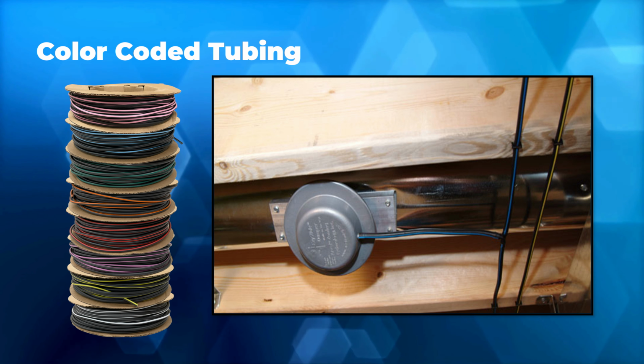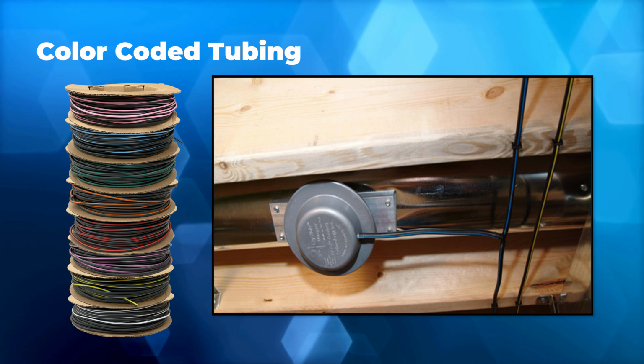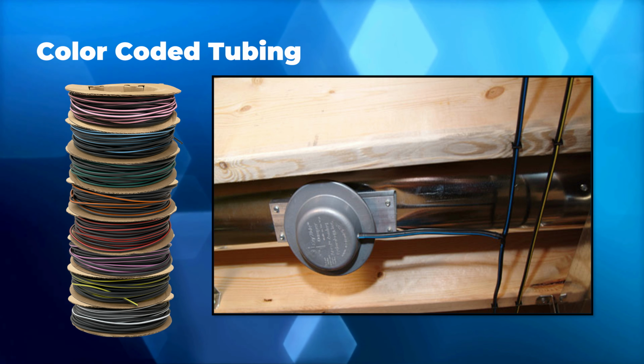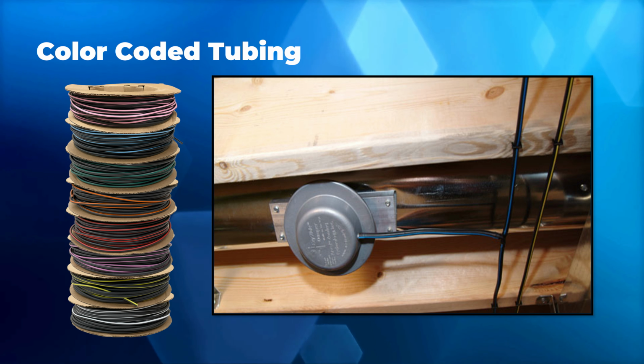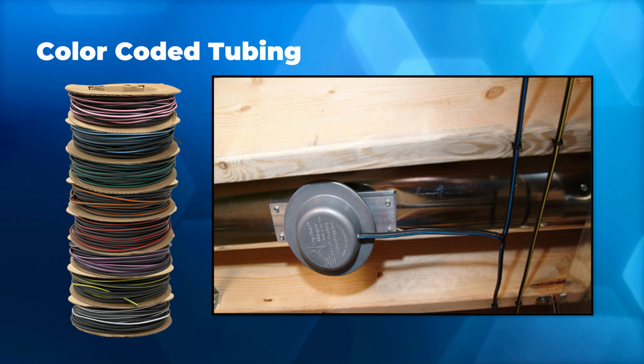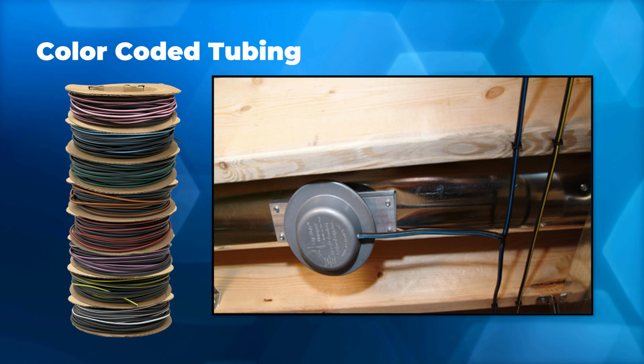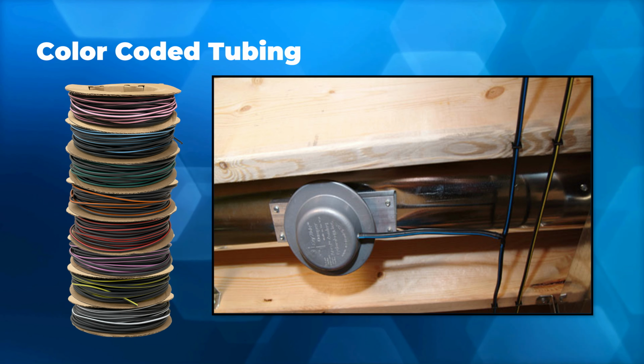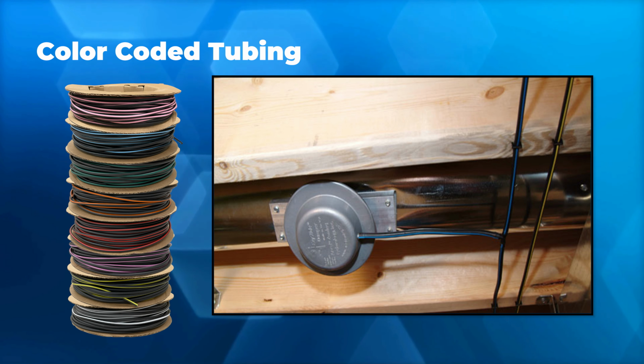That way, if a service contractor needs to go back and troubleshoot, it's easier for them to identify what dampers are on what zone. Especially when you're doing branch runs and you have 15, 20 different dampers on one job. Definitely speeds up if you ever have to do any troubleshooting or anything like that.